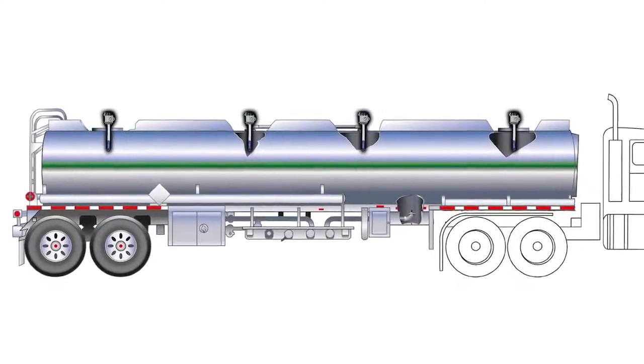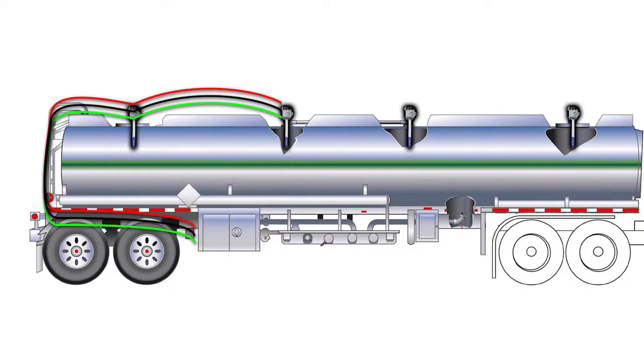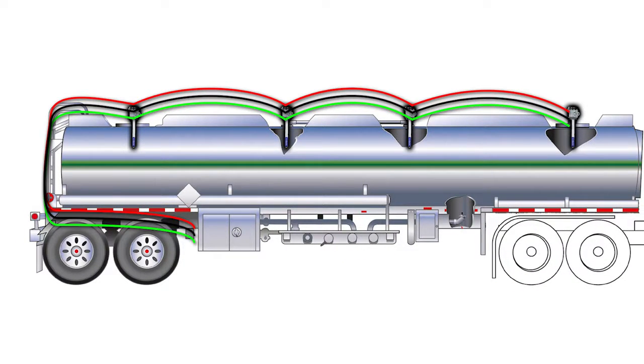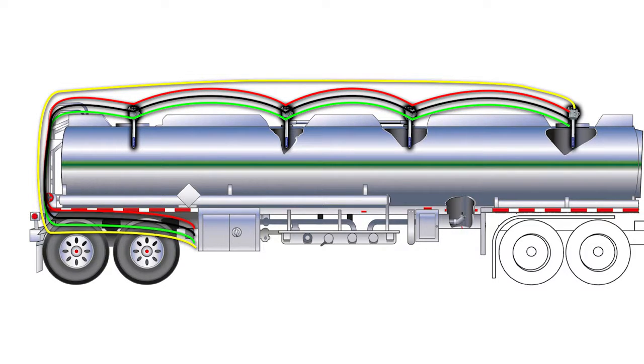The way a 5-wire system is wired is the red, black, and green wires are all wired in parallel. When the yellow wire reaches the number 1 probe housing, it is connected with the yellow wire of number 1 sensor. The orange wire coming out of number 1 sensor then hooks to the yellow wire of number 2 sensor. The orange of number 2 goes to the yellow of number 3, and this continues until you hit the last compartment of the unit. The last sensor in the trailer or tank, whatever the case may be, returns back down to the socket.